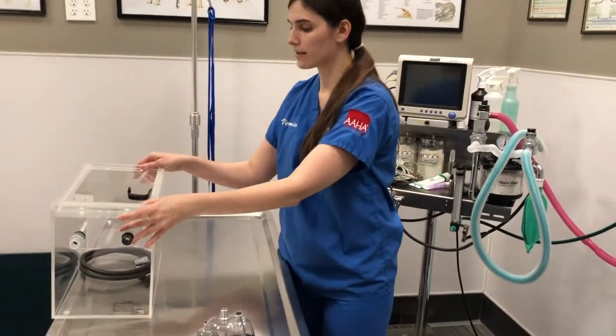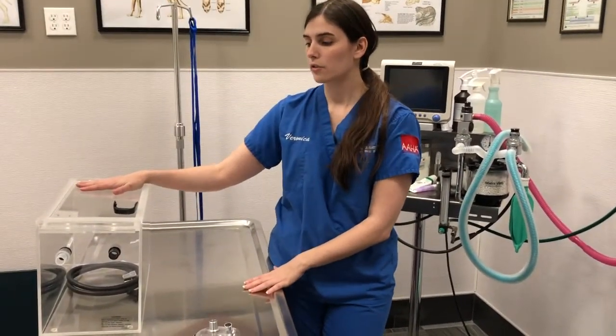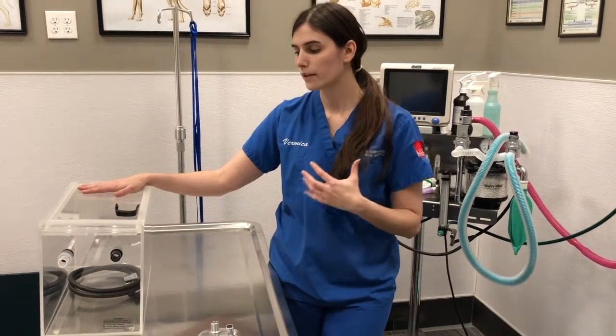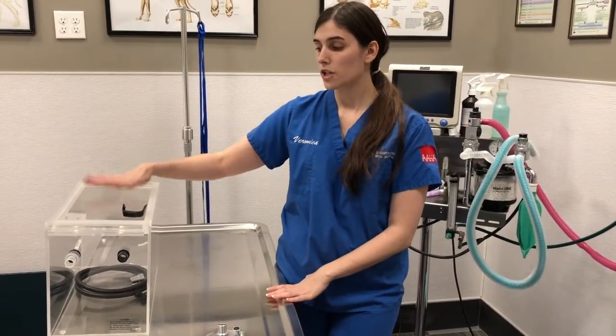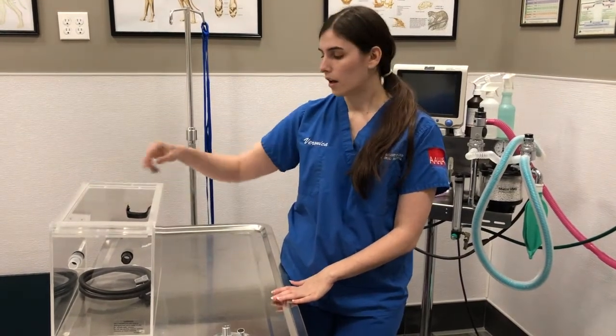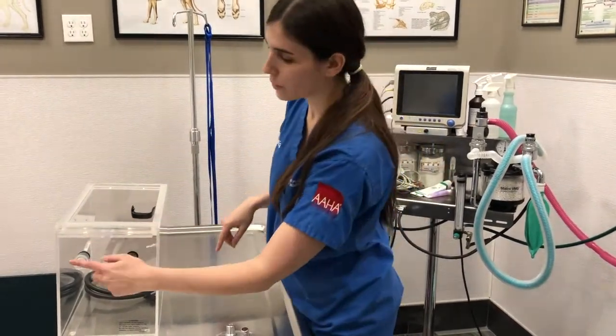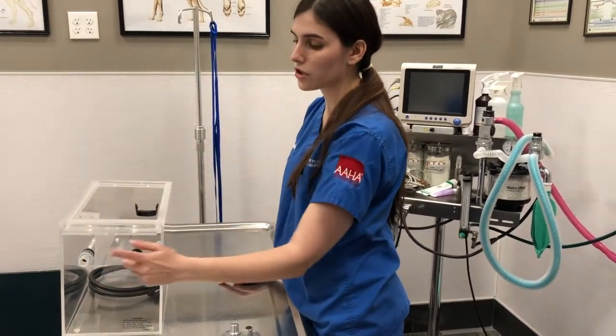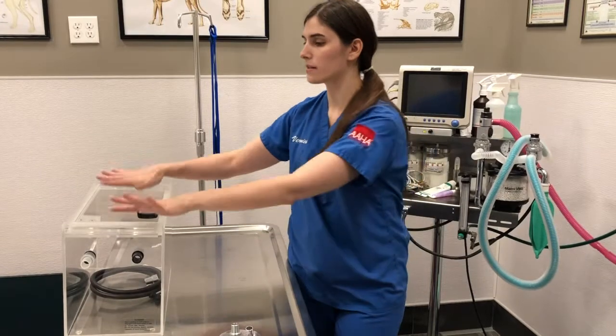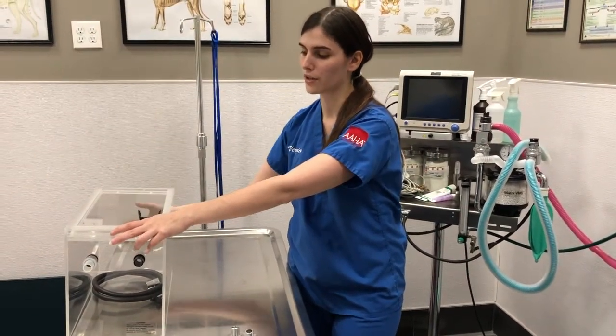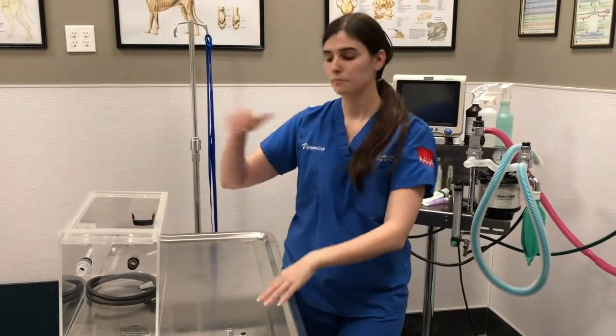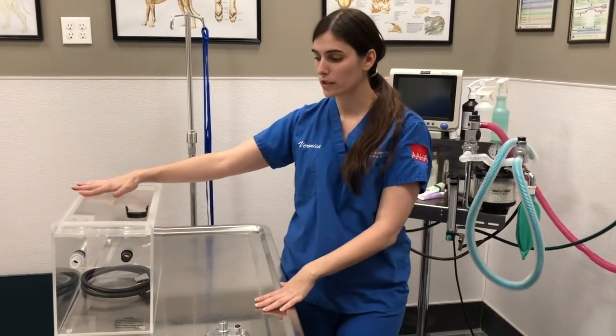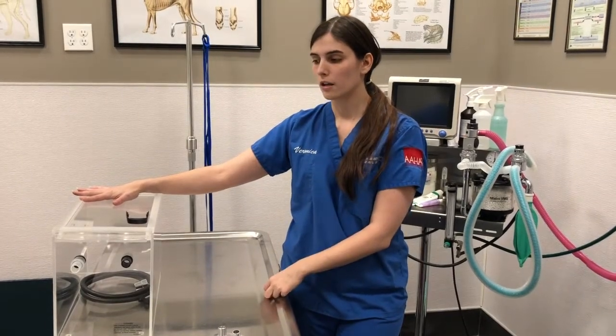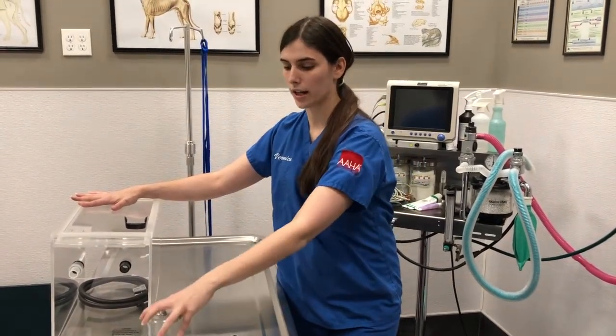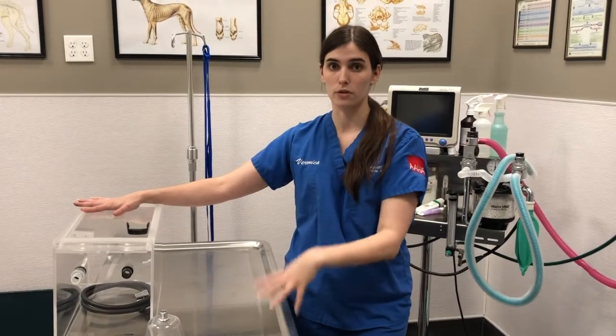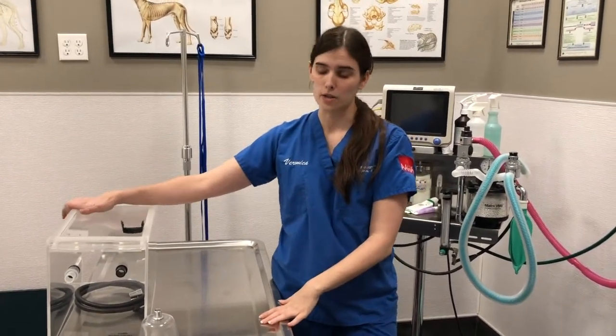And the last thing that we have here is an induction chamber. This is used for generally exotics like mice or rabbits, and is a chamber that can literally be filled with anesthetic gas when hooked up again to the system. So one end would be hooked up to the anesthesia and the oxygen, the other end would be hooked up to the scavenging system. And this is a sealed container that you would fill with anesthetic gas. Once the patient is asleep, we would take them out. But again, this is something that we generally don't use here at the practice. We have it just in case, but we find that these methods of anesthesia aren't as safe as having an endotracheal tube placed, so we try to have all of our patients intubated for anesthesia.